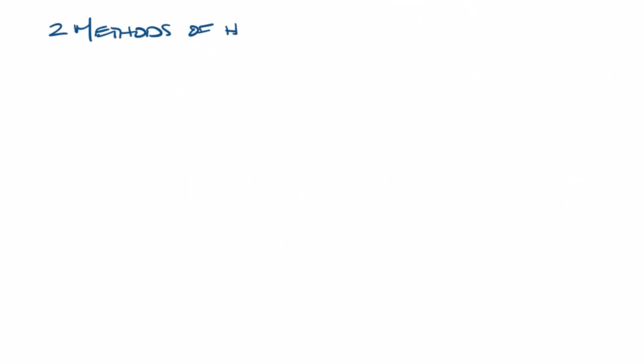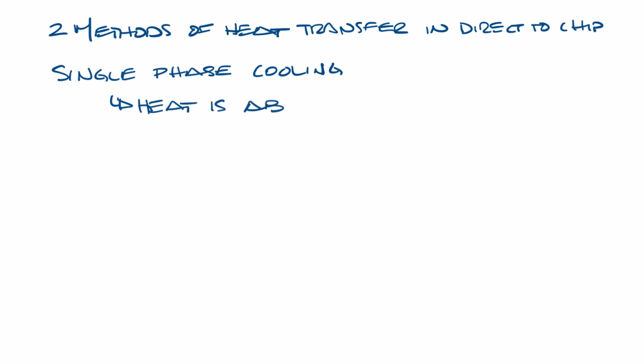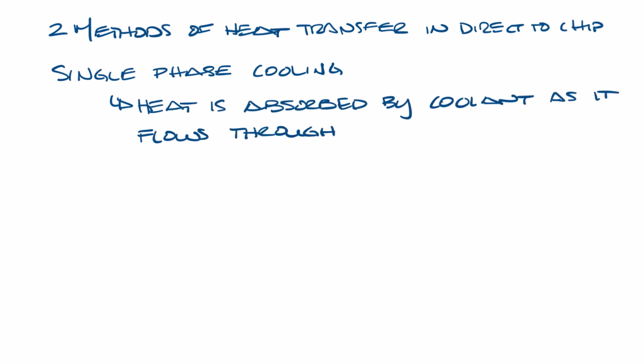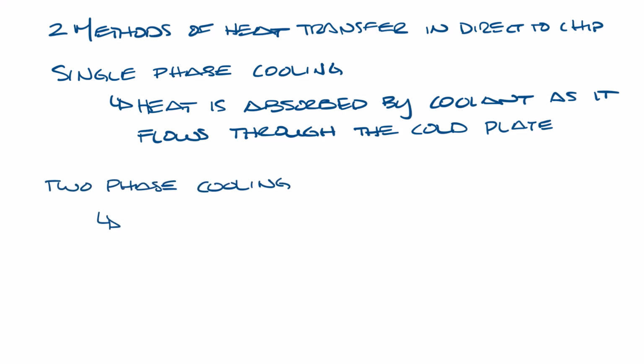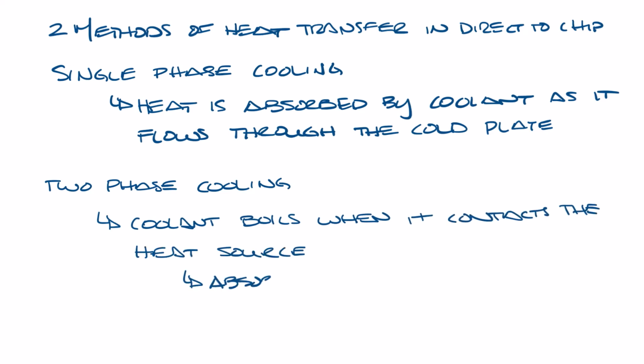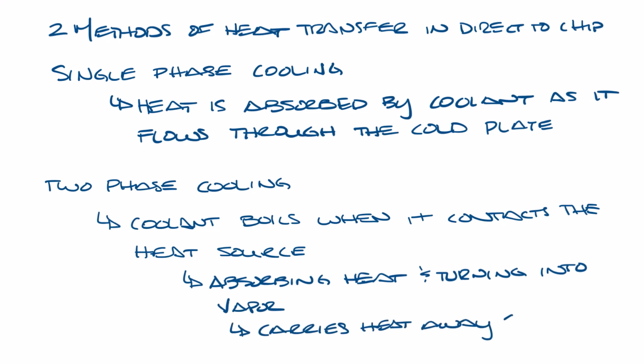There are two methods of heat transfer in direct-to-chip cooling, single-phase and two-phase. In single-phase cooling, heat is absorbed by the coolant as it flows through the cold plate, and the fluid remains in a liquid state throughout the process. In two-phase cooling, the coolant boils when it comes in contact with the heat source, absorbing heat and turning into vapor. This vapor carries the heat away where it's condensed back into a liquid somewhere else in the system.